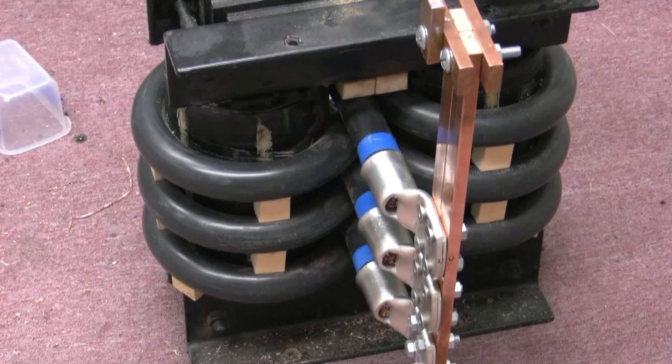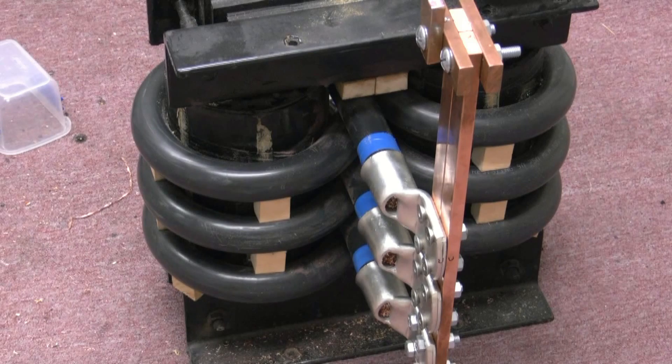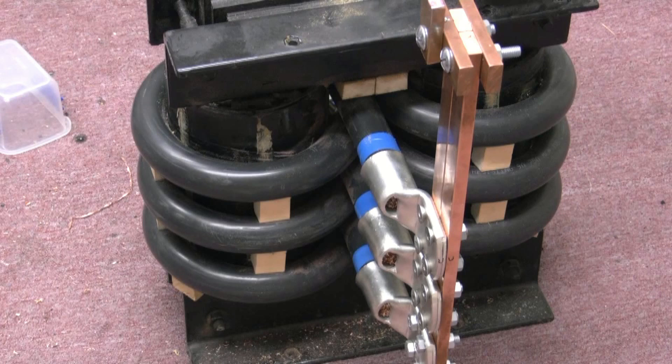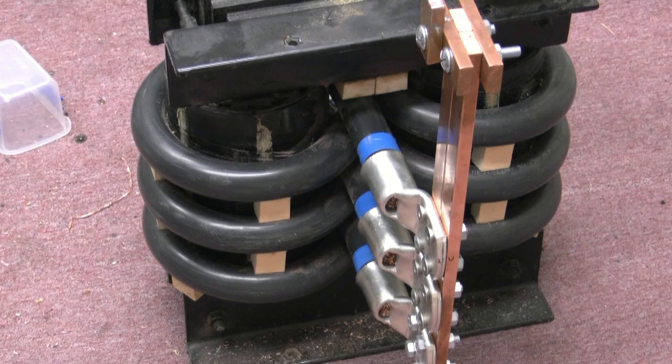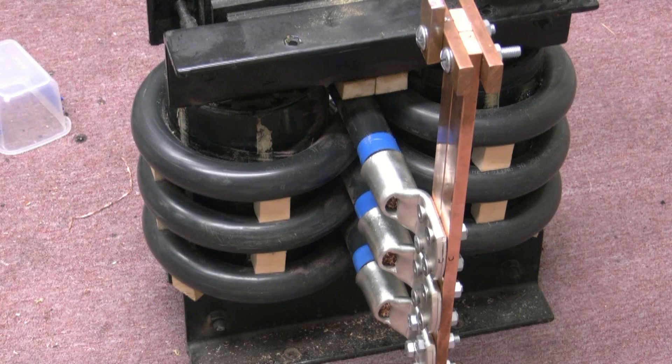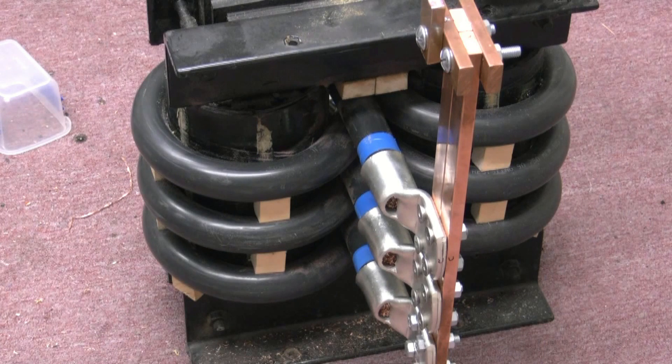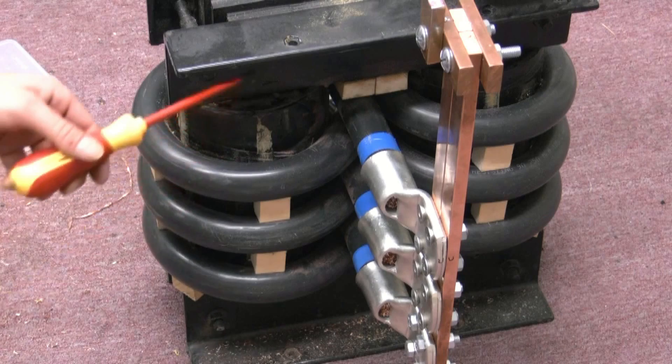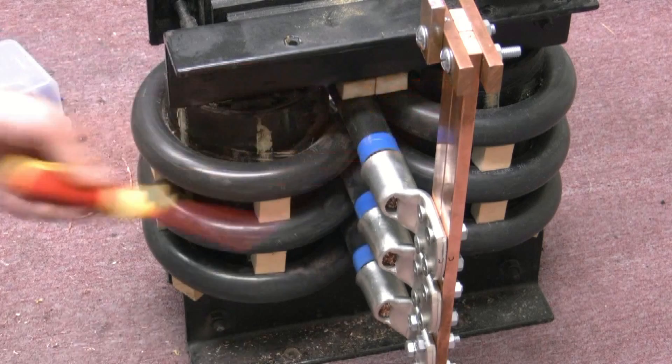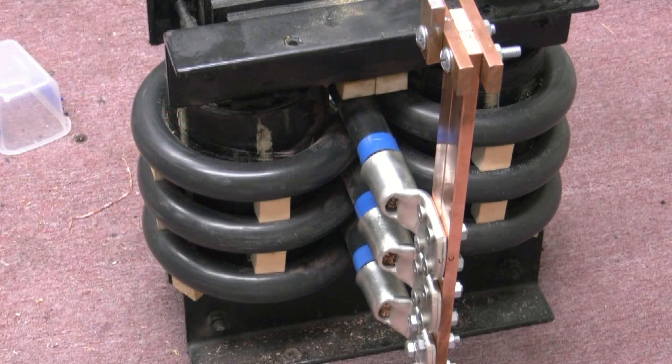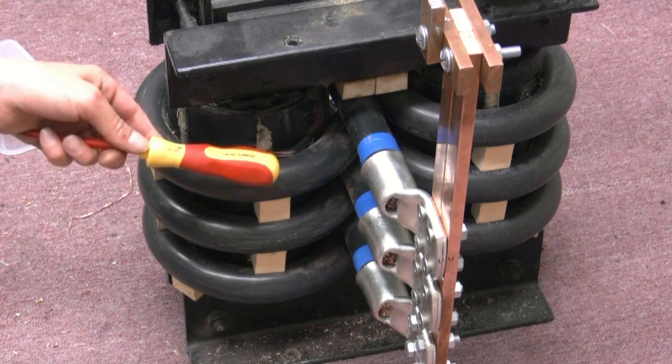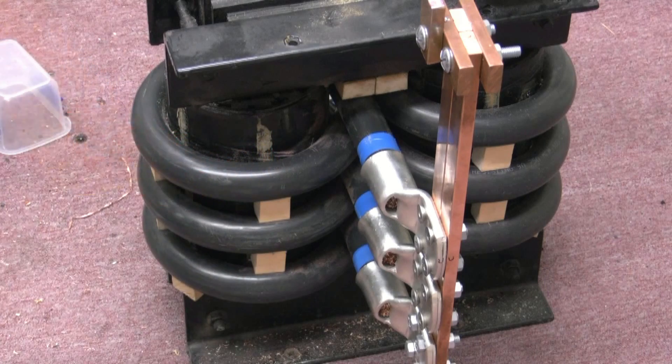Well I thought I'd better explain what I've done. For those interested in it, and if there's electricians watching this, even you guys probably think fucking hell. But, standard transformer, still don't know what the KVA rating is, but I reckon about 50 KVA, and we've got 120 volt winding, another 120 volt, both of those are in series, it runs on 240, and each one of these 400mm cables goes round in a figure 8.